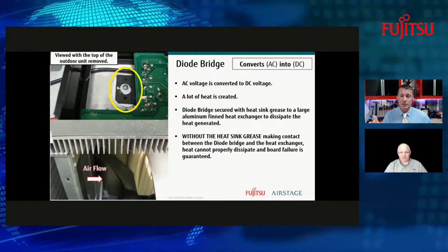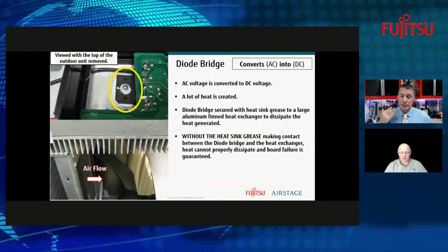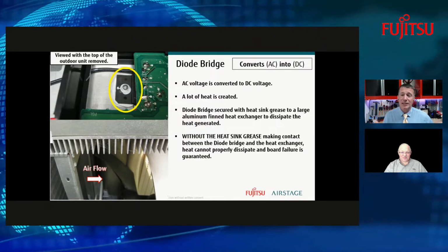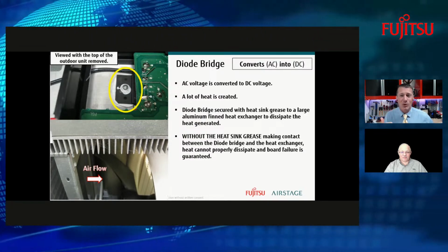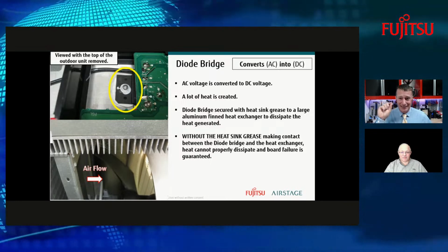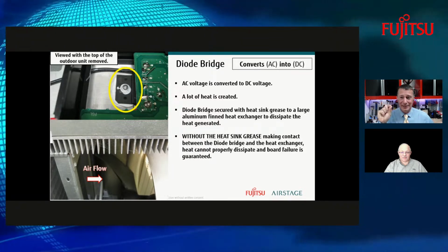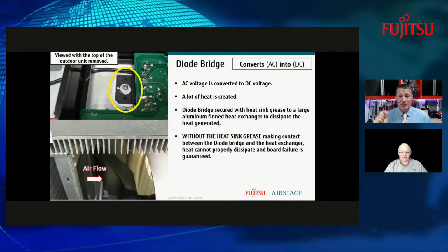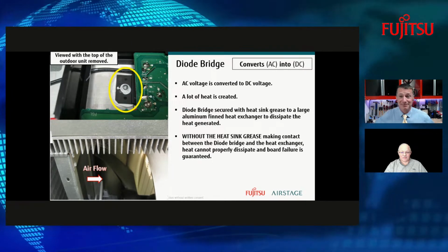I had that conversation just this weekend about doing service on these inverter systems. If you're only cleaning the surface of the coil and not looking to see that the heat sinks are clean on the inverter for dissipation, then you're not doing a complete service on that piece of equipment. That's correct.